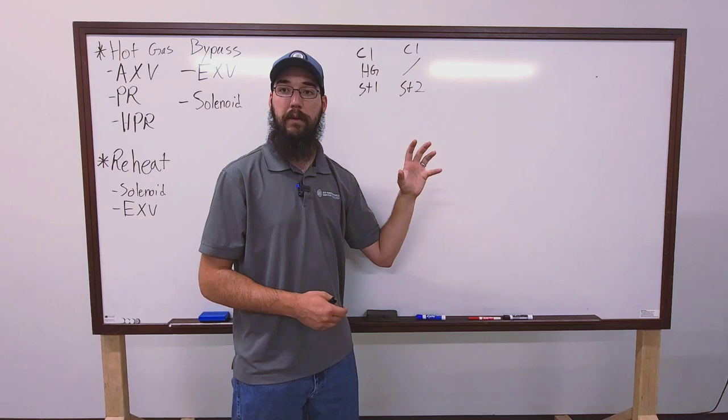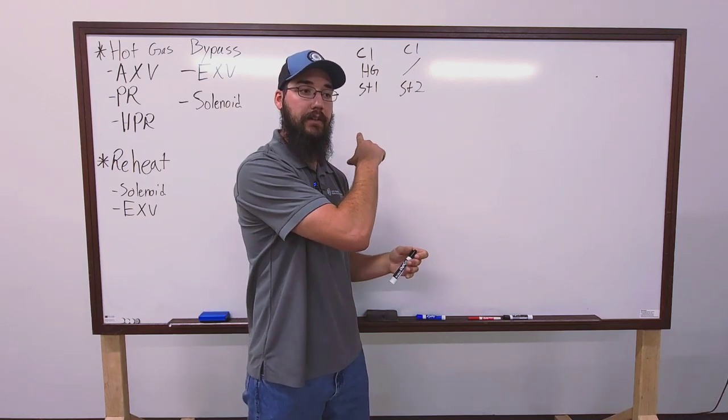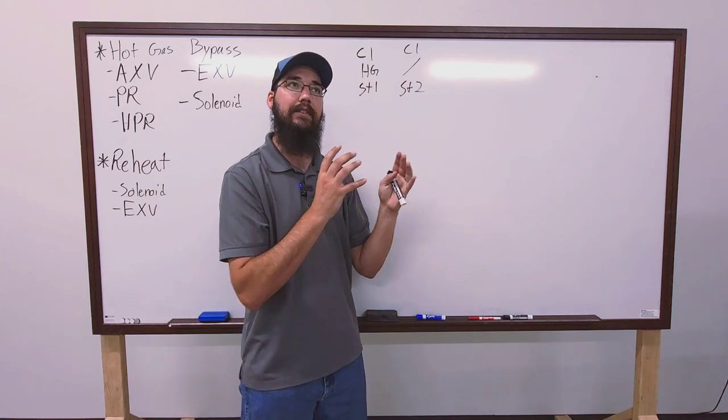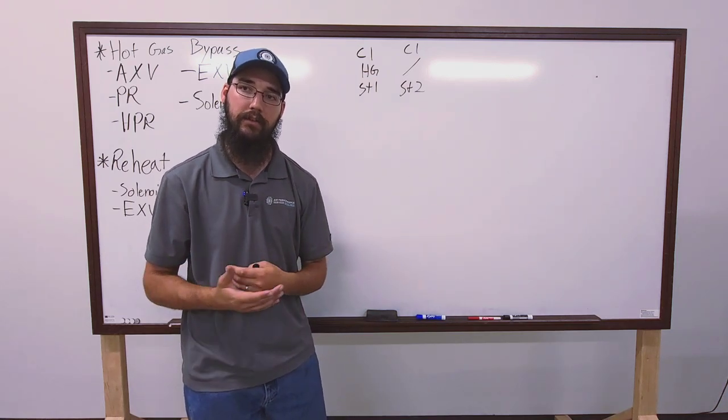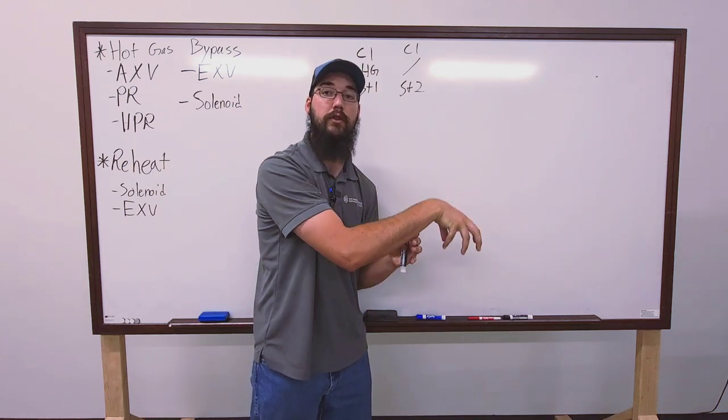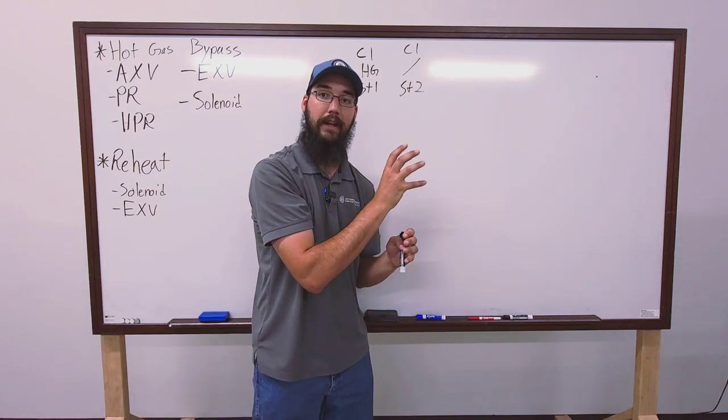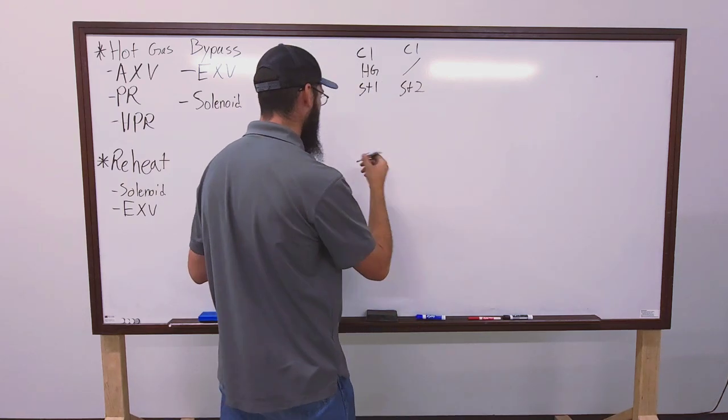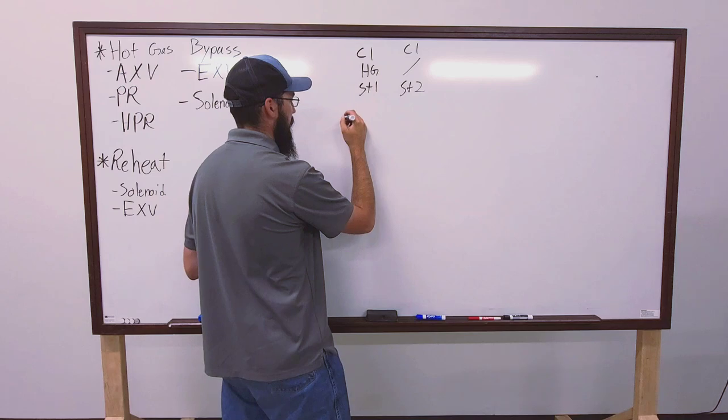So our solution is to stage that circuit back further by adding a hot gas into the suction. And ultimately, that is its main goal. And typically a system like this, a true hot gas, it's going to dump that in. I said the suction a second ago. I technically shouldn't have said it that way. It's going to put it into the distributor going into the coil, the evaporator coil.